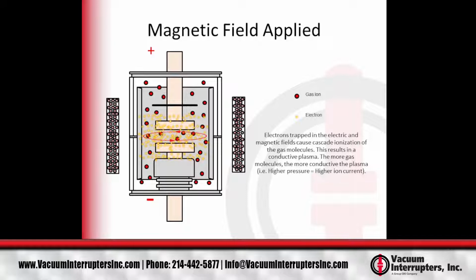So what this does is it generates electrons, which produces a current, but it also produces a conductive path through the vacuum, which normally there is no conductive path. So the amount of current that flows across this path is directly proportional to the internal pressure.